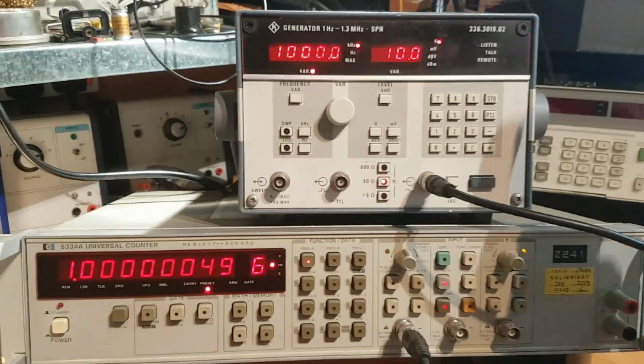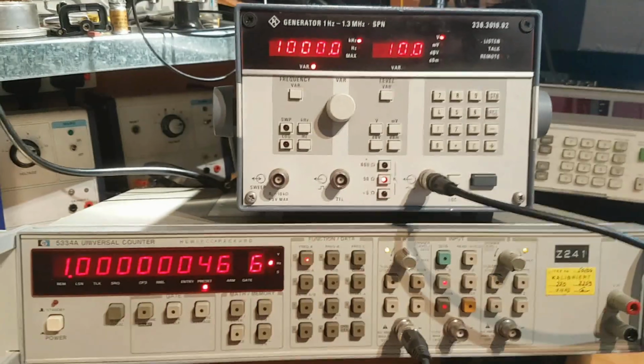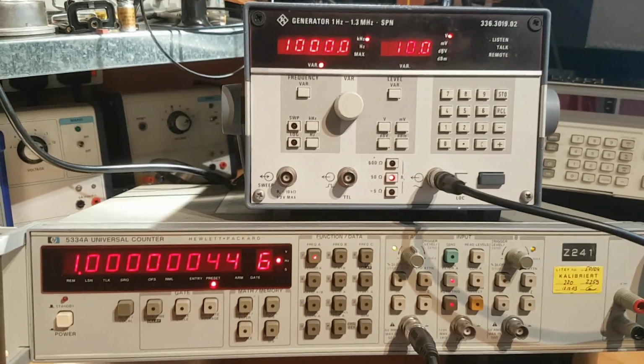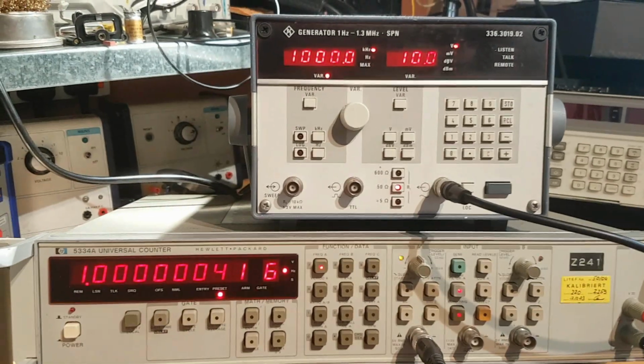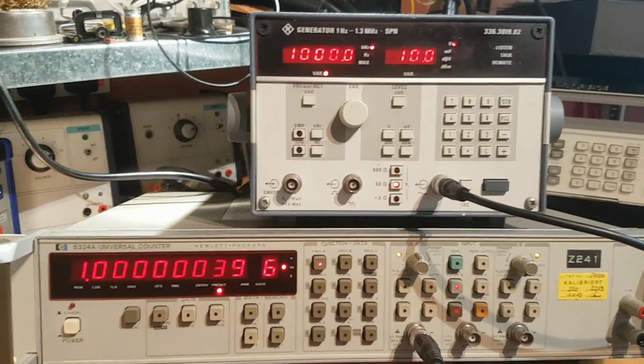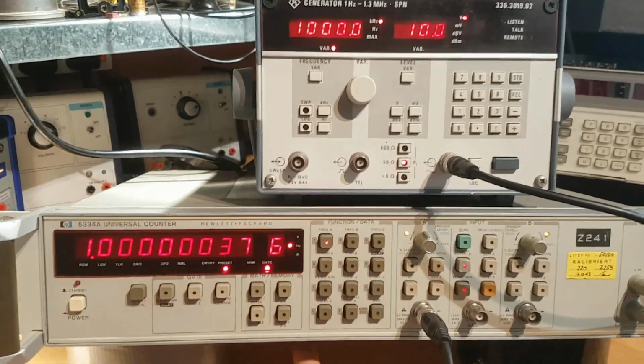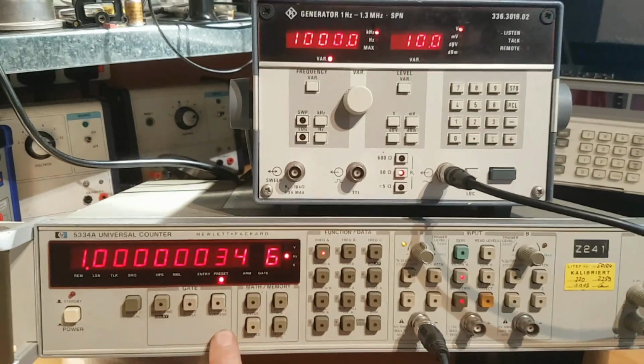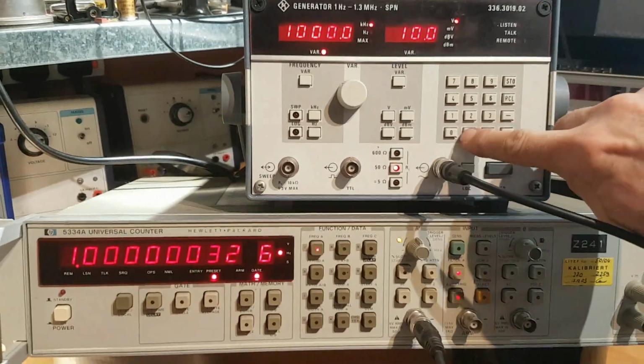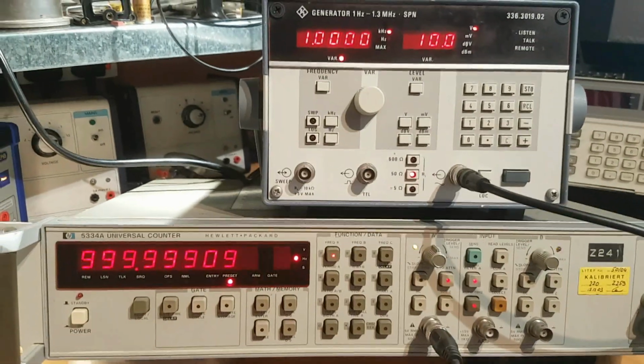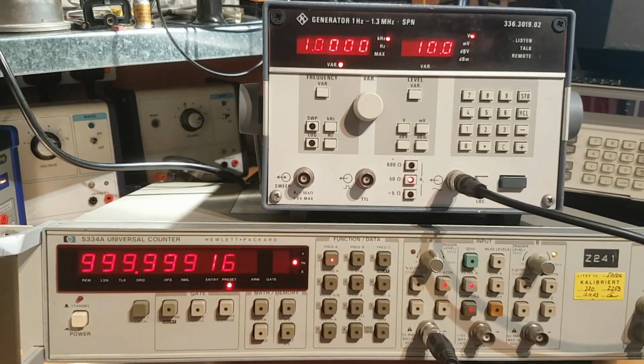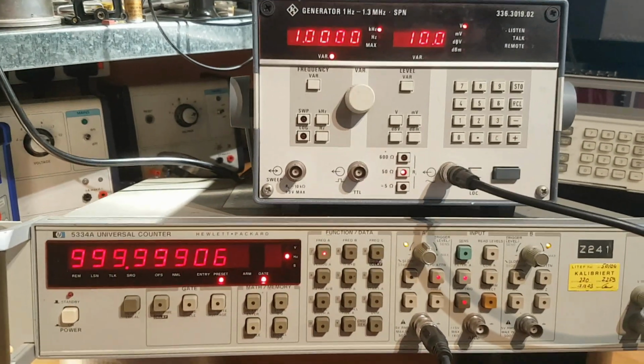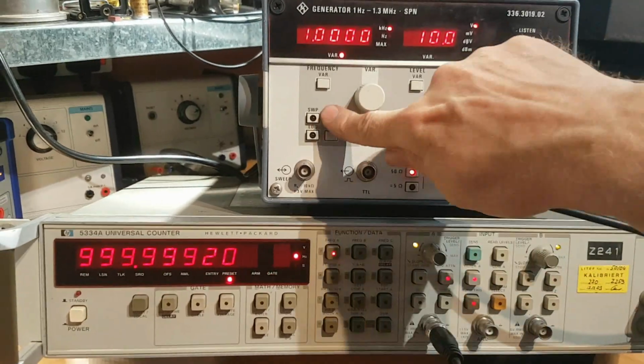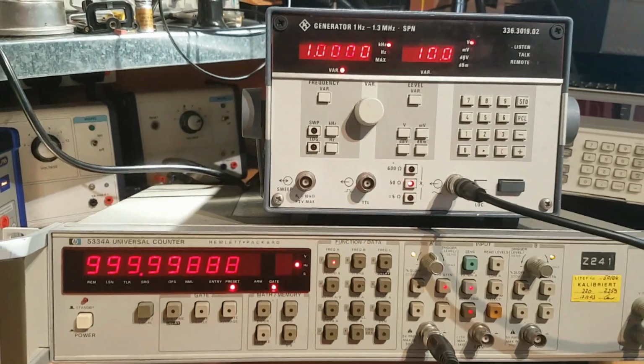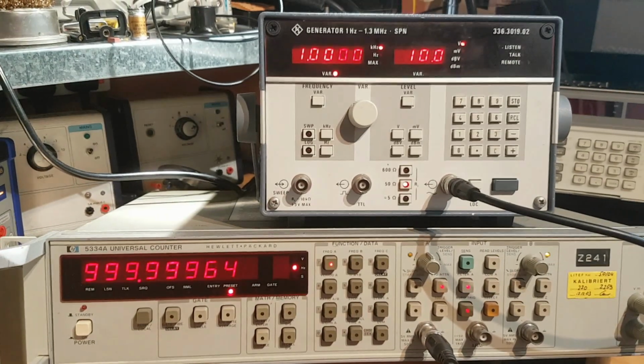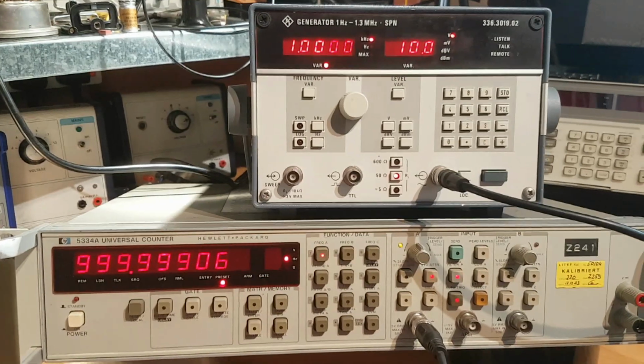And if you see one of these online, snap it up because it's a fantastic piece of kit when it's working. So that really concludes the repair. That's done. I'm going to do the voltage check and just check the calibration of the voltage, but the customer doesn't really need it calibrated, but this is calibrated, and that's working pretty close. So let's go back to 1 kilohertz again. I like that. There you go. Sorry, that was 1.0 kilohertz. There we go. It's warmed up slightly, drifted off, but it's pretty close to the stated amount.